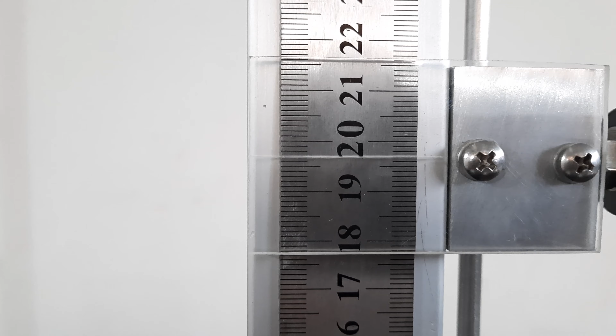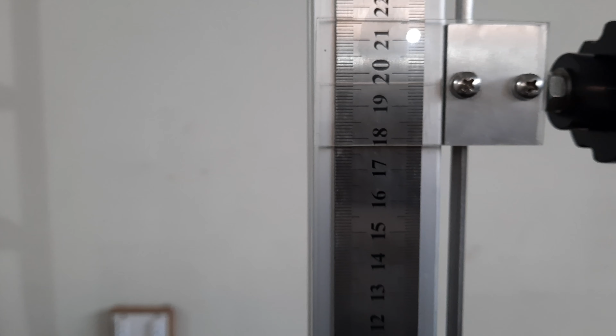Now I will loosen this screw and move the probe upward such that the tip just touches the water level. As you can see, the tip has gone down because the water level has increased, because we have turned on the pump and we have set the flow rate. So I have adjusted the probe. As you can see, the tip just touches the water level. Now we have the new reading, which is 19.2 centimeters. We will subtract the datum head, which was 17 centimeters, from this reading. Now this will be our head reading.